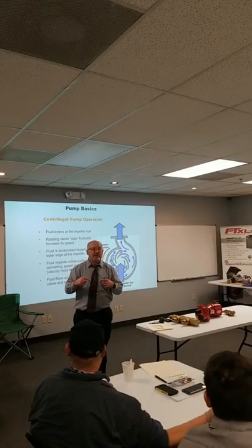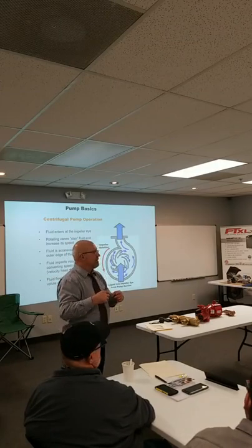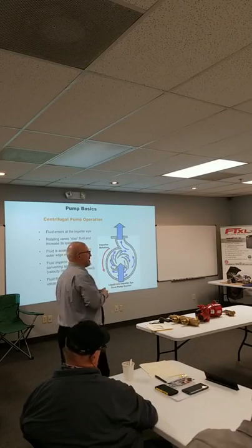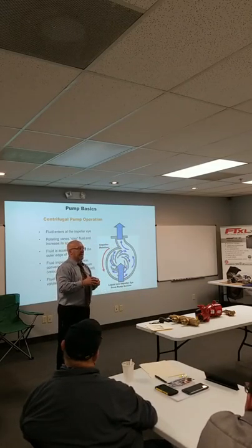If it's three phase, right, three phase. What did I say? Did I say single phase? You didn't mention that. Single phase, you just switch the start. Well, I said commercially, so to me, commercially is always three phase, but you're right. So three phase, if you switch it in the wrong order and change the direction, we have it all the time.